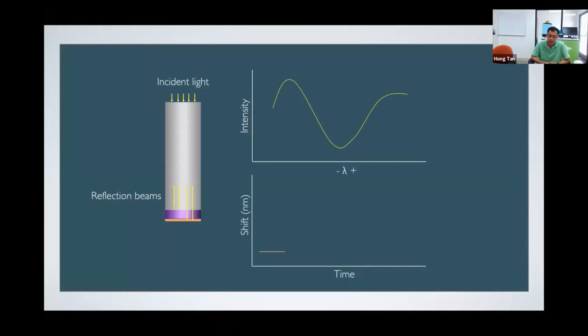Here's how it works. We shine white light into the other end of the probe. The photons travel down the probe to the detection end. At the interface of the probe and optical layer, one reflection beam reflects back. At the interface of surface chemistry and the ambient, a second reflection goes back. These two reflection beams interfere and create an interference pattern. It's an intensity of light at a certain wavelength.